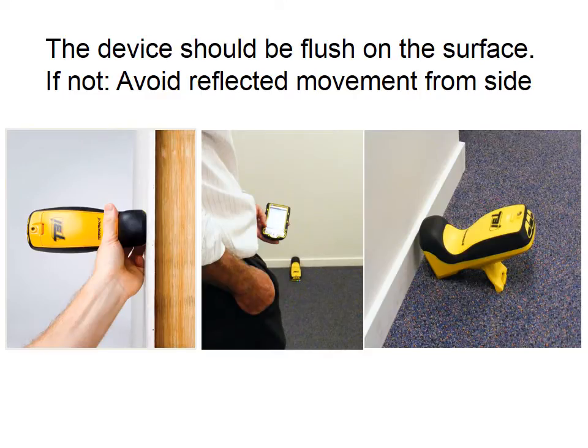The T3i device is designed to be used flush against the surface where at all possible. However, it does still work effectively while using the flip stand on the 45° or slightly off the surface, but we do have to avoid reflected or sideways movement, which can affect our readings.